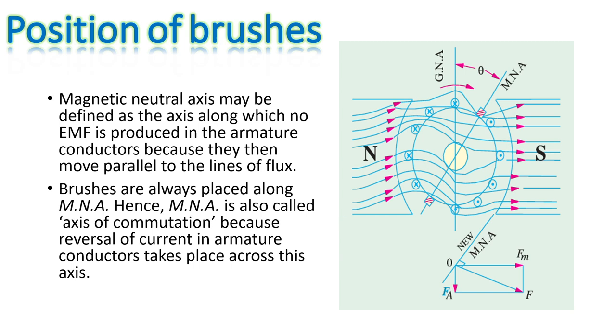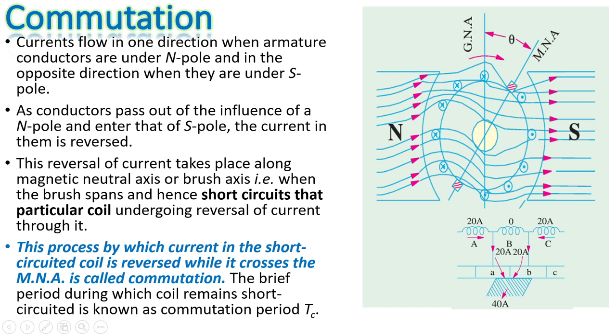The position of the brushes is of vital importance. The magnetic neutral axis is defined as the axis along which no EMF is produced in the armature conductors, because they are moving parallel to the lines of flux. Brushes are always placed along the magnetic neutral axis; hence the magnetic neutral axis is also called the axis of commutation, because reversal of current in armature conductors takes place across this axis. Current flows in one direction when armature conductors are under any one pole — for example under the north pole — and in the opposite direction under the south pole.